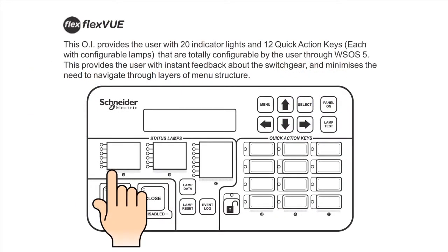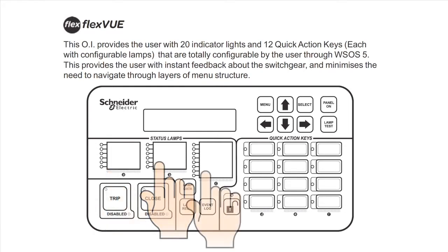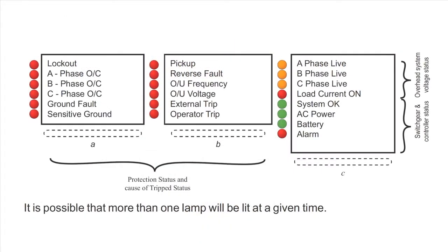Indicator lamps. These lamps are used to provide instant indication of the controller and switchgear status. Depending on the configuration, the lamps can be red, green, or orange, and on, off, or flashing. The multiple colors allow for grouping of similar functions. For example, red for protection, orange for voltage, and green for system health. Insert cards with the headings of the programmed functions are inserted into the A, B, and C banks so as to define the purpose of each LED. The configuration of the status lamps can be changed within WSOS version 5.